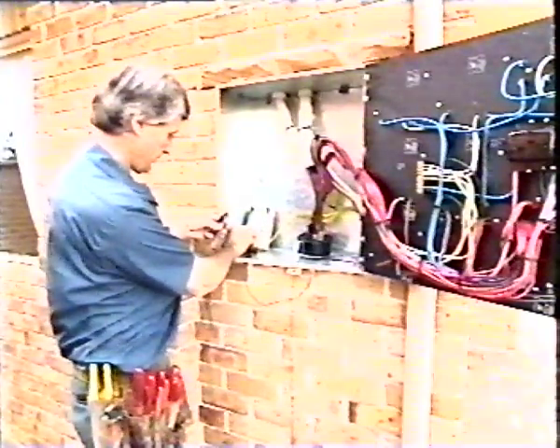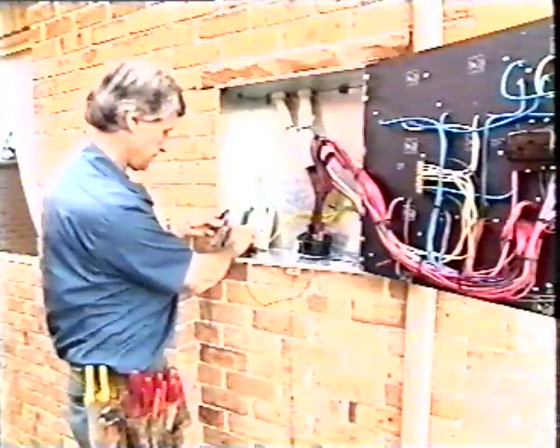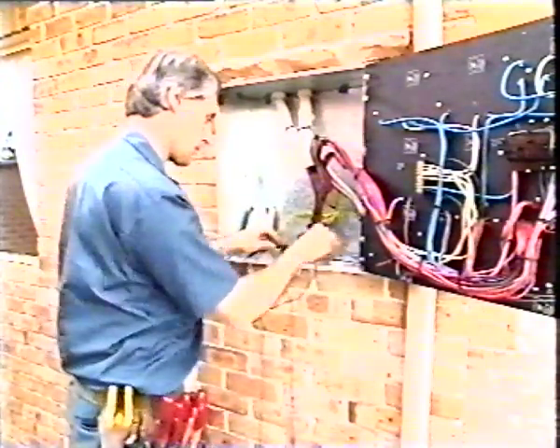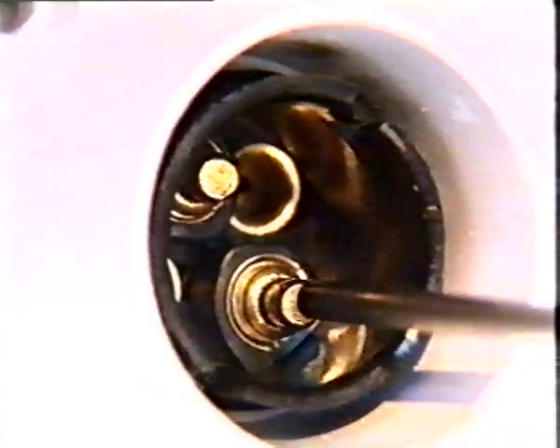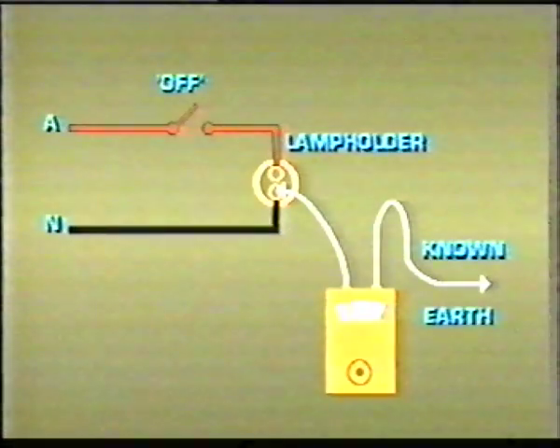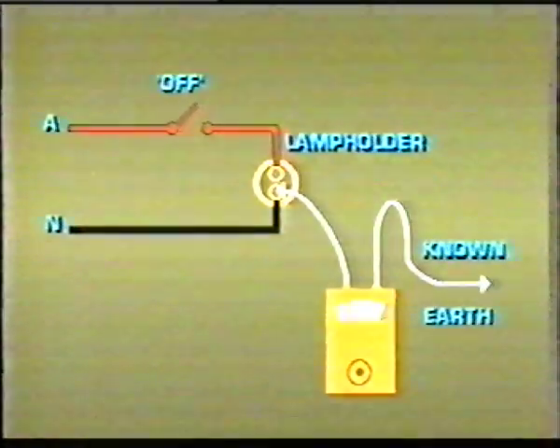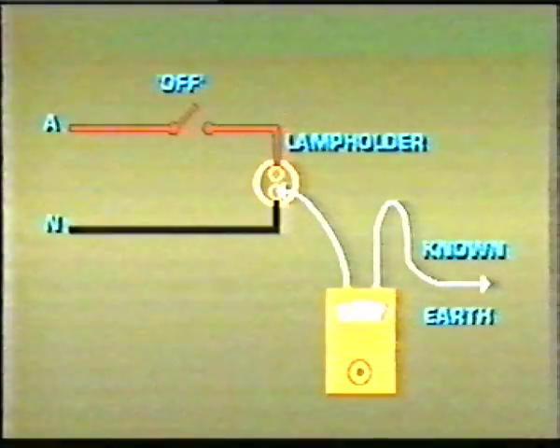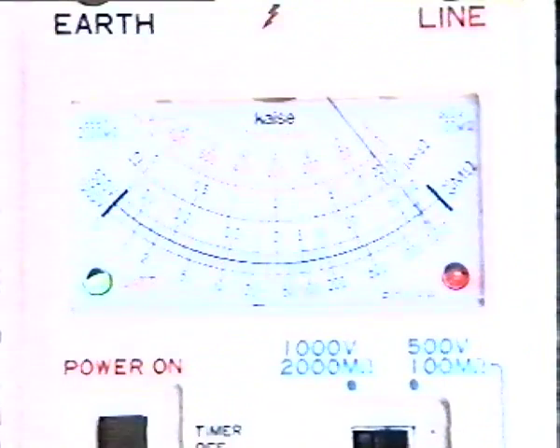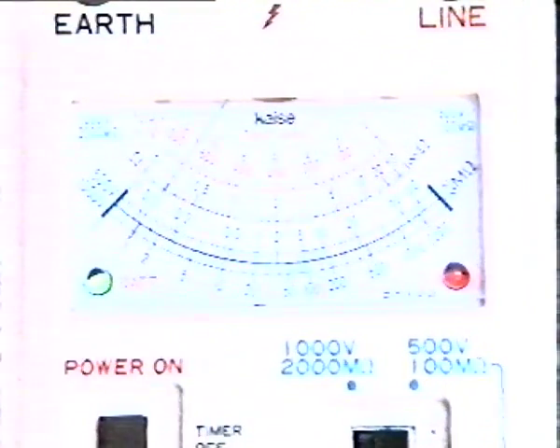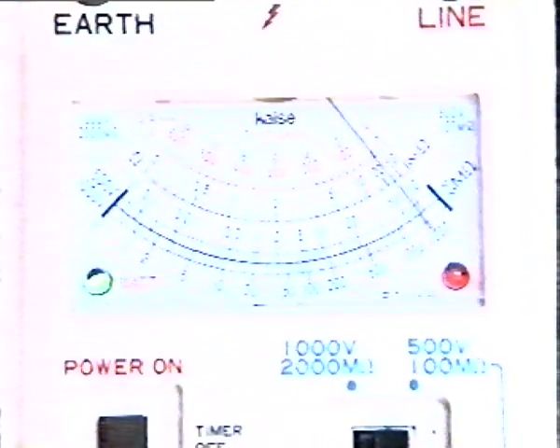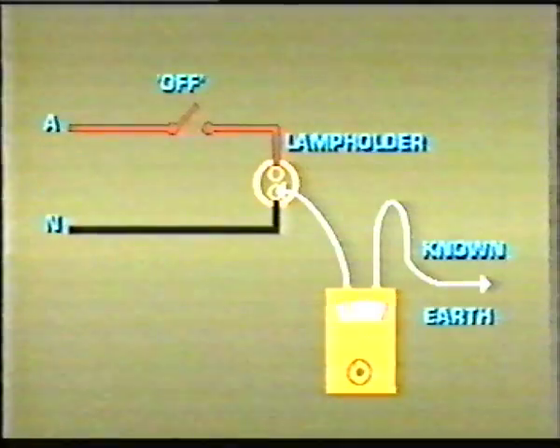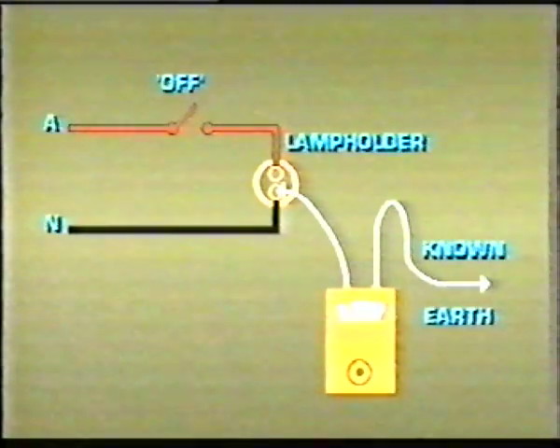Earthing continuity has been proved by earlier tests, as in test A, and the MEN connection is intact. A lamp holder is tested by an ohm meter with one probe on a contact and the other to earth. The switch is in the off position. Reading indicates a short circuit at one contact. This is correct. If the switch has been connected in the neutral conductor, a short circuit would not have been indicated at either terminal.